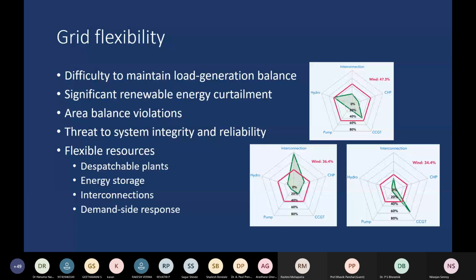For instance, in Gujarat, a few years ago, a very common problem in the morning was that when the solar would ramp up, all the transmission lines connecting the thermal generators, the coal-based generators, to the grid would become underloaded and as a result would see significant overvoltages. This overvoltage would result in reactive power flowing into the generator rather than being drawn out of the generator. So in the morning, the generator would start operating at leading power factor, and this would lead to stability issues and the generators would eventually trip. This problem was solved to some extent by installing shunt reactors at the generating stations, which would consume reactive power and be switched on in the mornings so as to keep the voltage under control and reduce overvoltage.